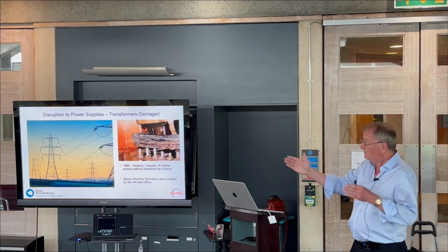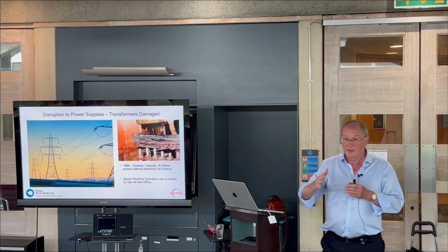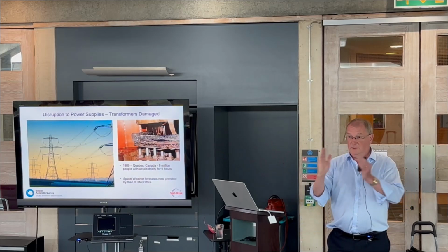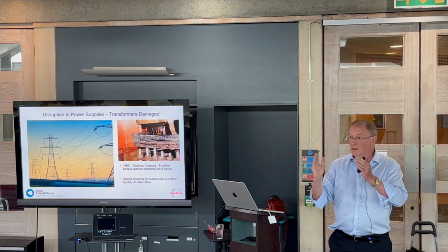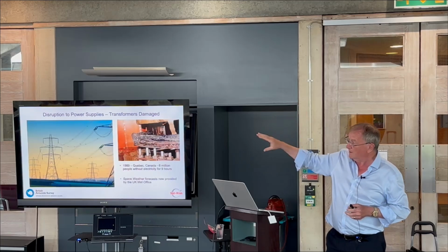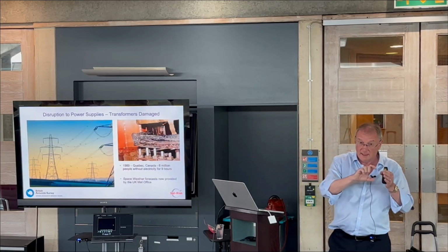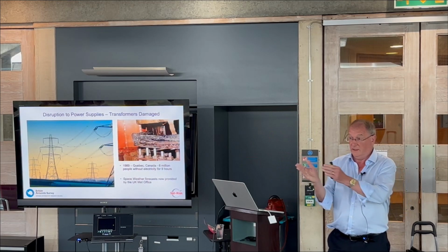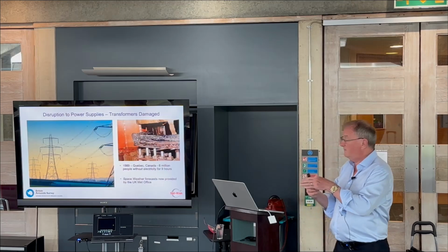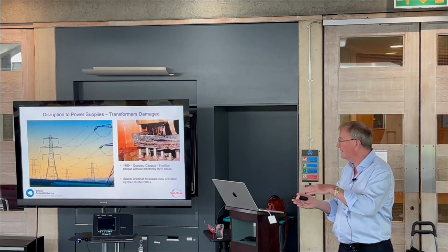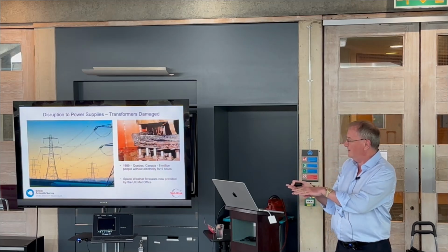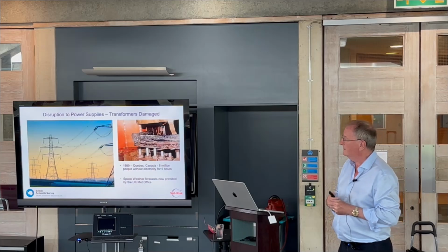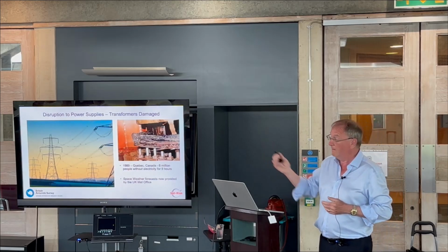Now, our power grid, of course, it carries huge electrical currents, but it's an AC current, it's alternating, it's always changing. When the aurora comes along and generates these currents, these are direct currents, okay? And that's a very different thing. So they shift the whole level of the current system out of the design specification of the transformers in the system.